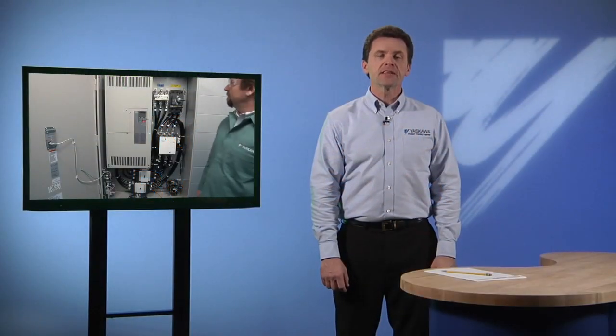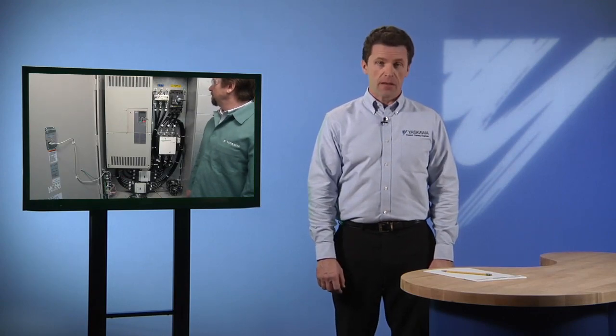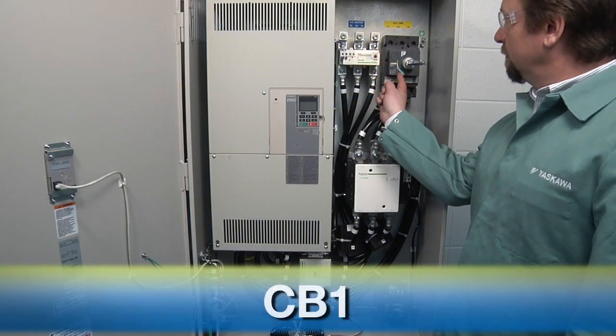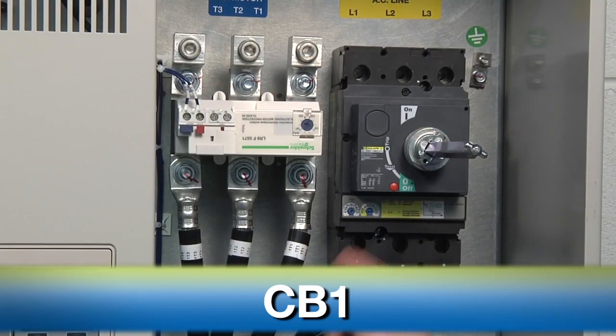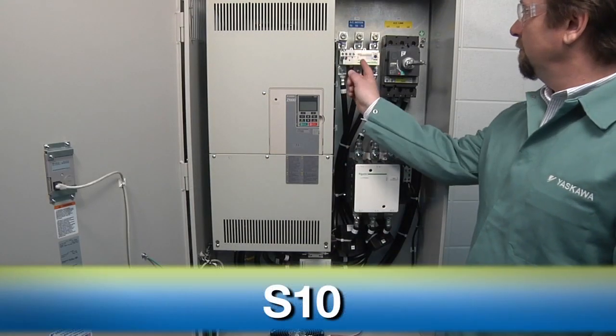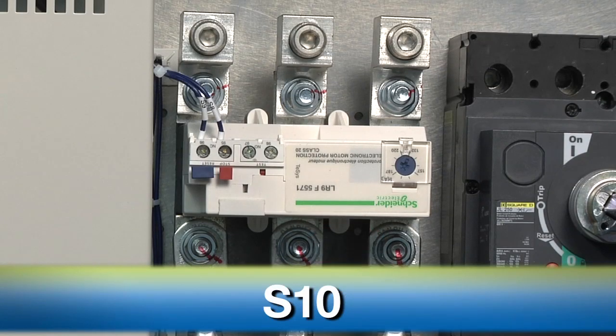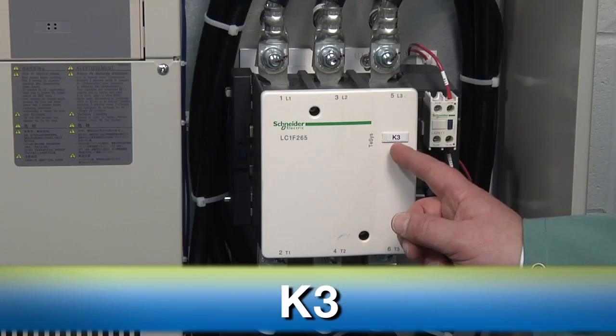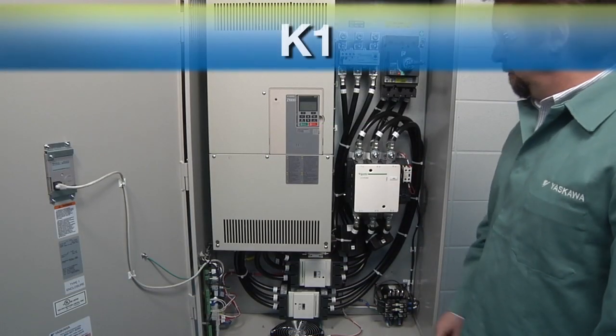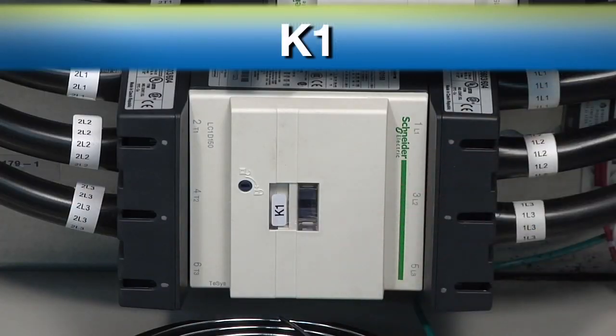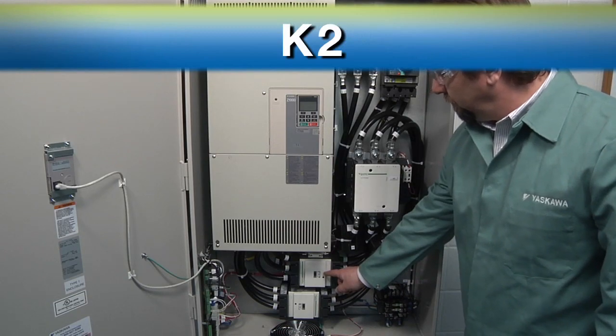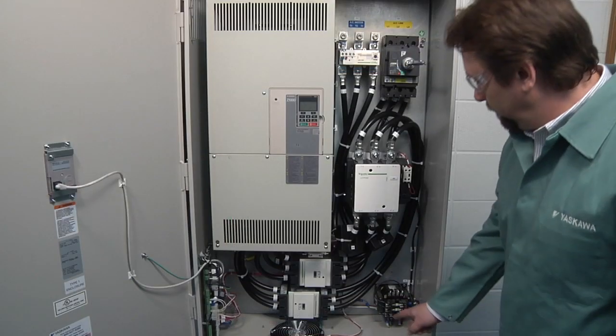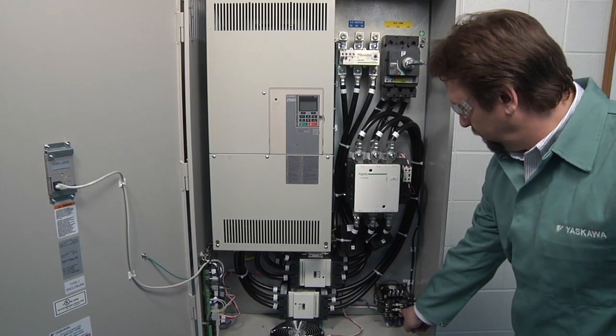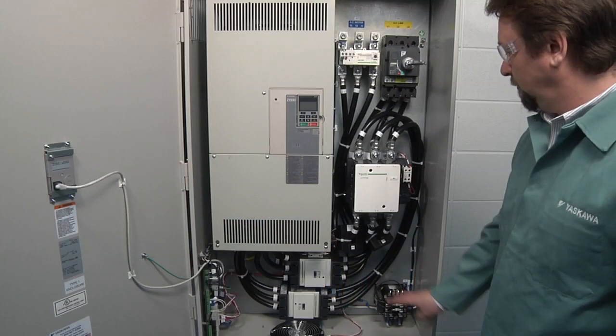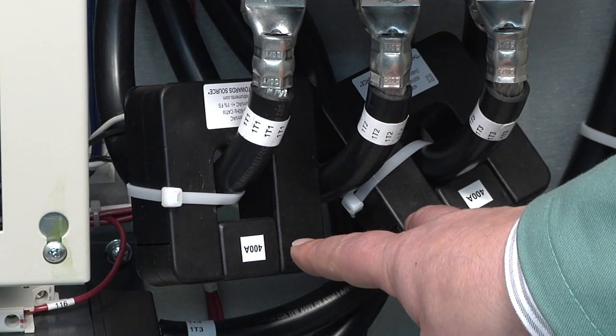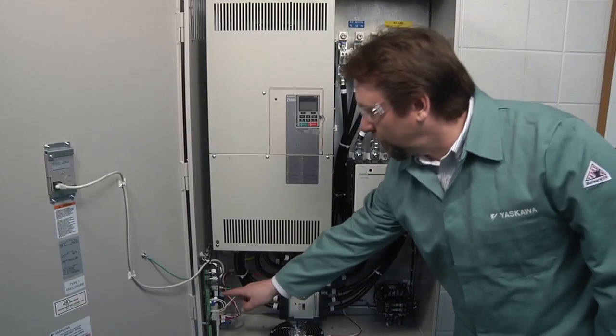Before we begin, let's get the lay of the land by identifying the components in the bypass cabinet. The circuit breaker is referred to in the manual as CB1. The motor overload is identified as S10. The bypass contactor is K3. K1 powers the drive, and K2 connects the drive to the motor. The control power transformer supplies power to the logic components. The two donuts are current transformers, which measure the output current and bring the information back to the bypass control board.